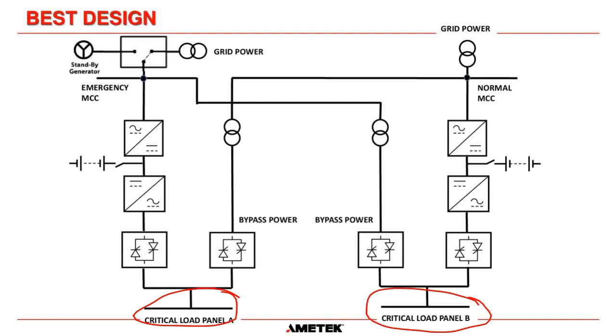And this is really more for DCS systems more than anything, because most modern day DCS systems, whether it's Delta V or Yokogawa or whatever it is, they are now designed so that the power supplies into the DCS systems have at least 2 AC inputs, if not 3 AC inputs. So if it has 3 inputs, you could have critical load panel A feeding input 1, critical load panel B feeding input 2, and then another grid supplied distribution board feeding input 3 on the DCS panel. And that way you get even more redundancy on your system.